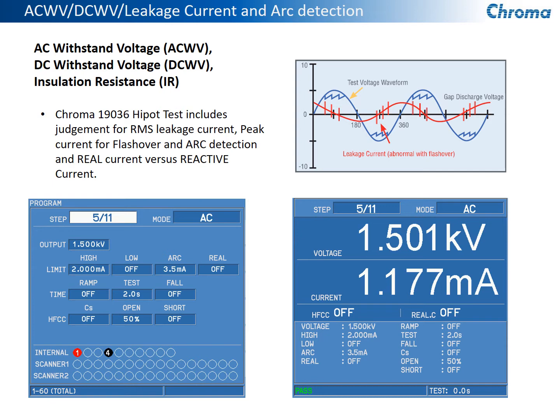It also includes something called a high frequency contact check. This is unique for detecting the actual unit being attached to the device under test. So it ensures that the 19036 Chroma test equipment is physically connected to your device under test. We'll go into a little more detail on that later. Down below you'll see internal scanner 1, scanner 2. This is where you select the various channels that you're using for this particular test. And I mentioned before that you can go with our 2 additional optional scanners all the way up to as many as 40 individual channels. On the right-hand side, you're going to see the actual display of the results of the test. I like it. It gives you a great big reading of voltage and current for the AC high-pot test, but it also gives you down below the actual parameter settings for the test itself, as well as pass-fail data.